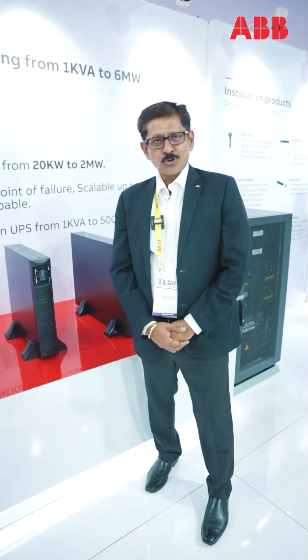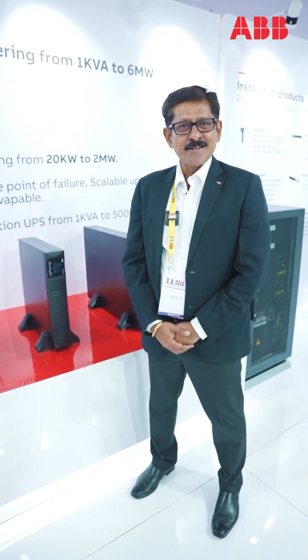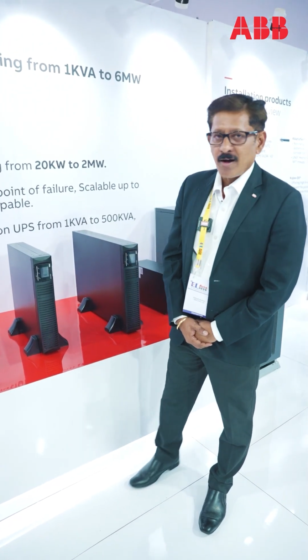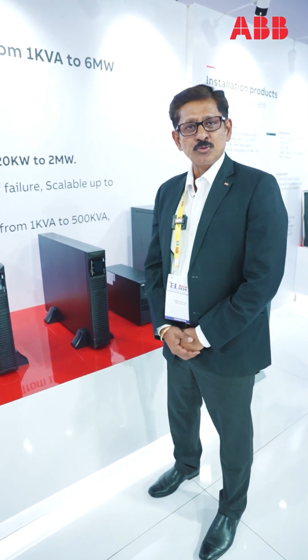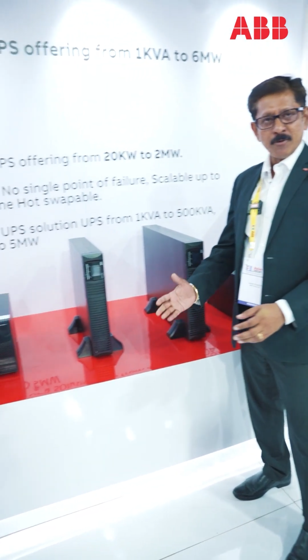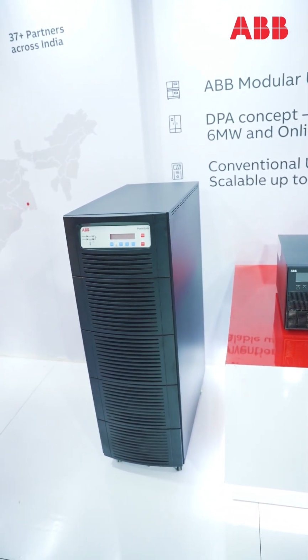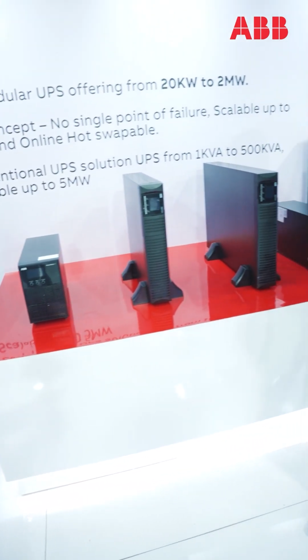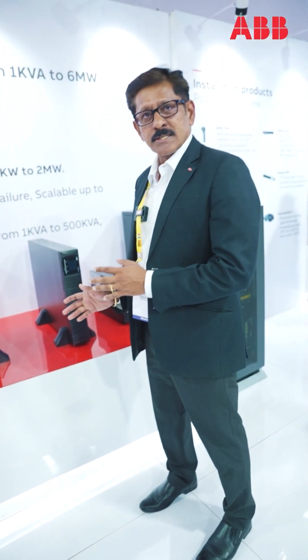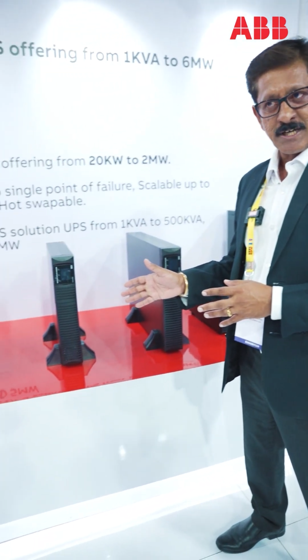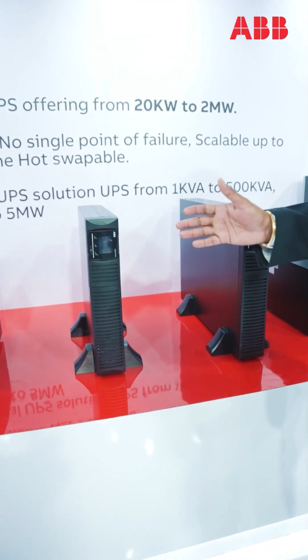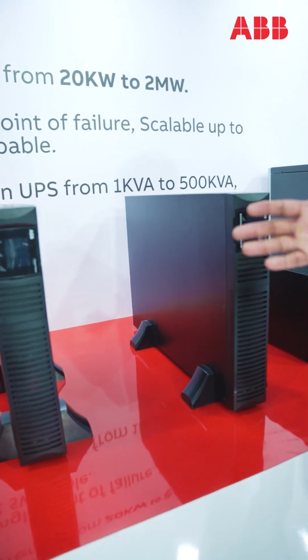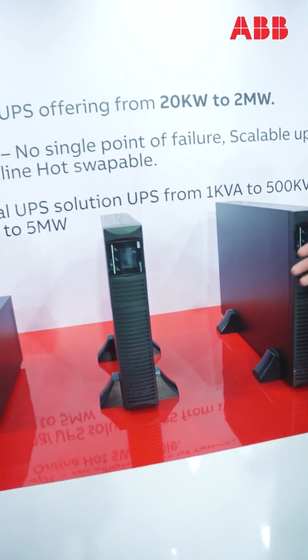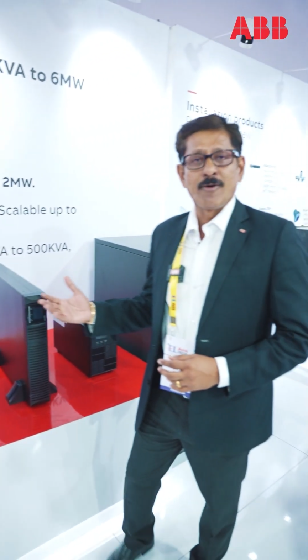Hi, myself Ashok Kumar, I am a UPS expert, and at ABB we offer from 1 kVA to 6 megawatt. We have single phase UPS ranges, which start from 1 kVA to 10 kVA. We have both versions here: one is a tower model and another one is a rack RT model. In this model, we can provide inbuilt battery solutions as well as external battery solutions. With inbuilt batteries, we can give 10 minutes backup, and with external batteries, we can give 30 minutes to 1 hour backup.